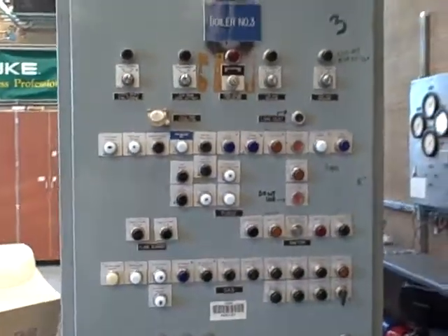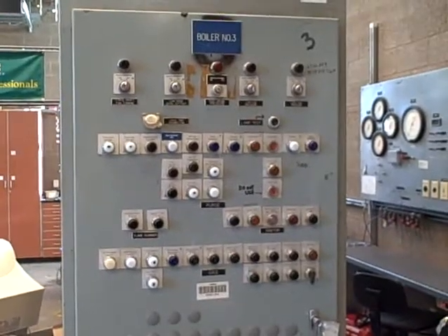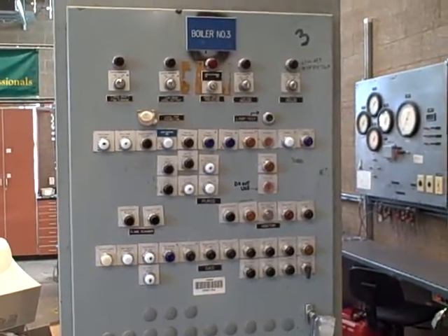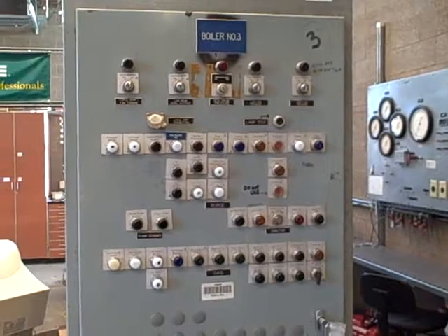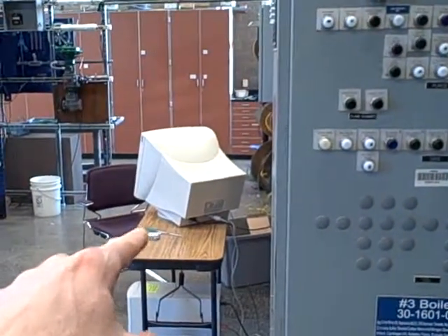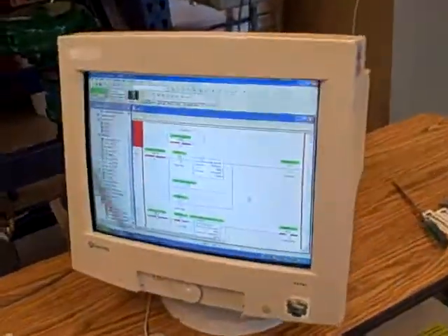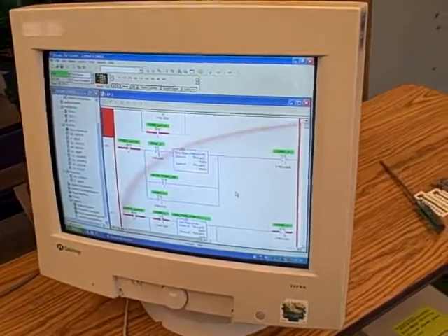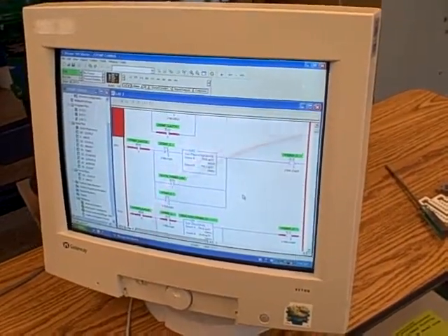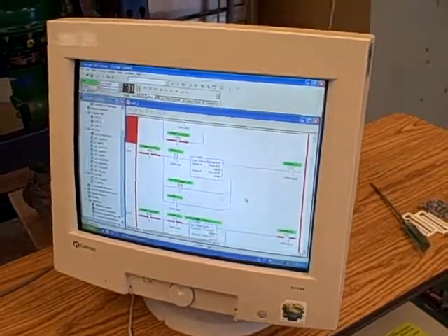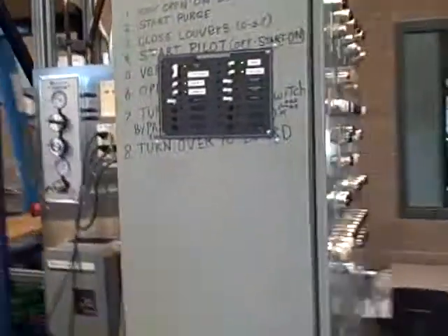Specifically, we're going to place real hardwired faults into the system. We're going to have students of different teams go in and diagnose what the fault is using the PLC ladder logic editor as a troubleshooting tool. By looking at the editor and watching the status of the contacts, we're able to tell what switch conditions are being made, which switches are not being made, and determine what the wiring fault is. Maybe not determine exactly, but give us good hints on where the wiring fault might be. So PLCs are powerful tools not only for controlling real processes, but also for diagnosing those processes they are controlling.